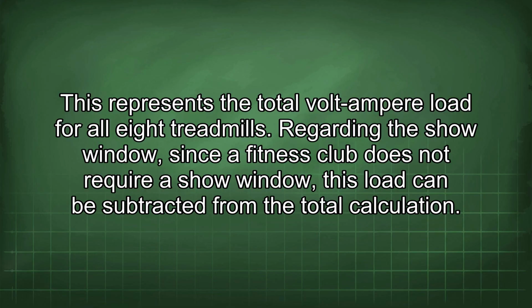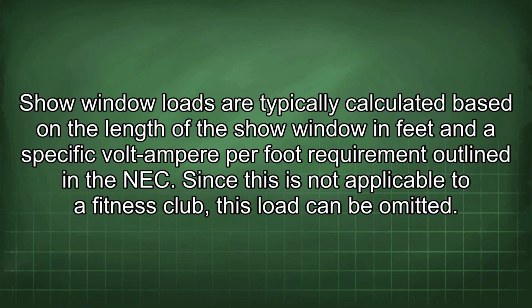Regarding the show window, since a fitness club does not require a show window, this load can be subtracted from the total calculation. Show window loads are typically calculated based on the length of the show window in feet and the specific volt-ampere per foot requirement outlined in the NEC. Since this is not applicable to a fitness club, this load can be omitted.